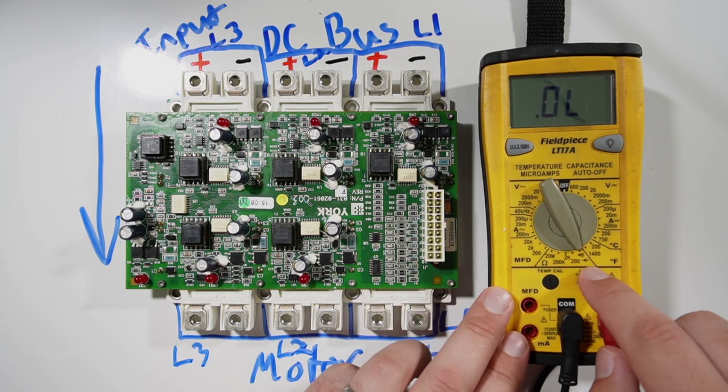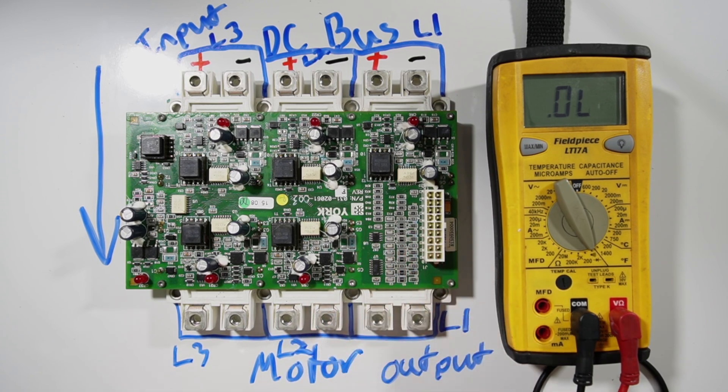Our meter, make sure that we're in our diode test mode and make sure your meter is capable of reading in diode. We're going to be looking for two different readings. We want to see either the VDC reading of the factory officially says 0.3 to 0.4 VDC, or we want to see a flat OL. I have a slightly modified version of that. With my background in electronics and dealing with diodes, we have a much more refined number of 0.34 to 0.38. That is the typical number we're going to be shooting for with something like this. But the factory does give a much broader official determination. As long as you are in between 0.3 and 0.4, you're considered okay.